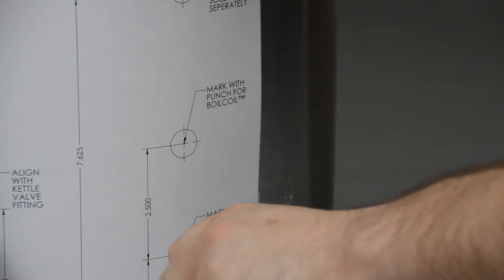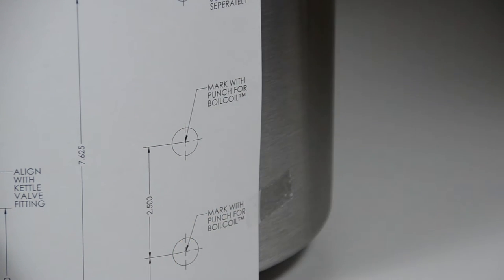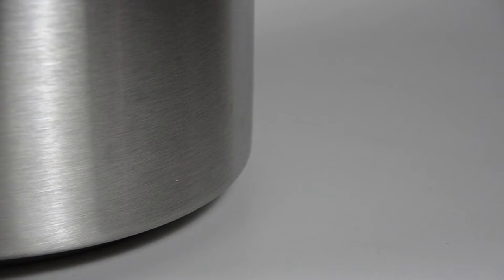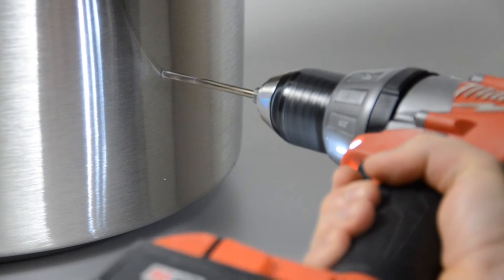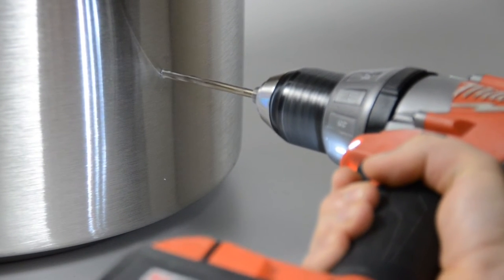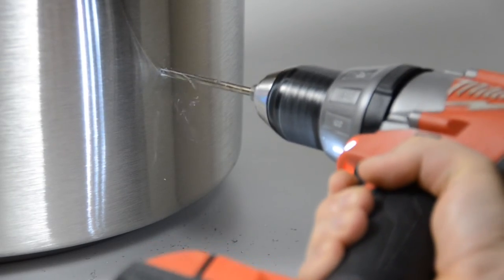Locating the holes accurately is critical to the installation of the heater coil. If necessary, use the automatic center punch multiple times to increase the depth of the indentation. Make certain the center punch marks are indented deep enough to prevent the drill bit from moving off the mark when you start drilling.